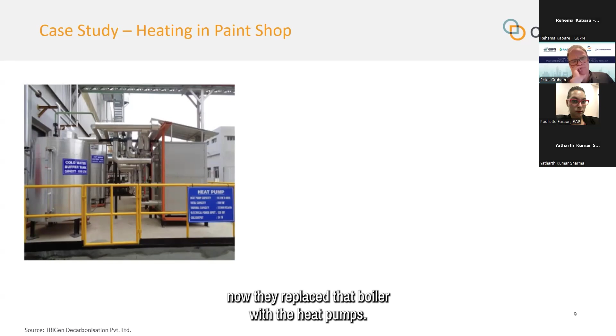They found that their energy bill reduced by almost 67%. Earlier their primary energy source was LPG, and after installing the heat pump, their primary source of energy changed to electricity, using a water source heat pump. Earlier they used almost 650 kg per day of LPG, plus 700 kilowatt hours of electricity. After replacing with the heat pump, they use almost close to 1800 units per day. The energy bill before installing the heat pump was around 12 million, and after installing it reduced to 4 million — almost a 67% reduction.